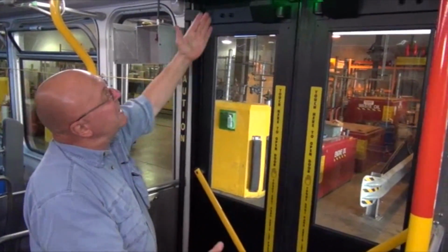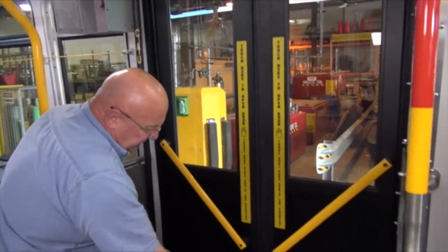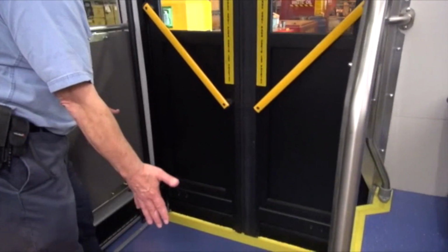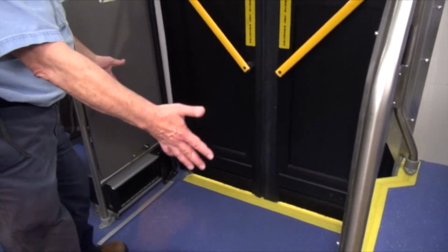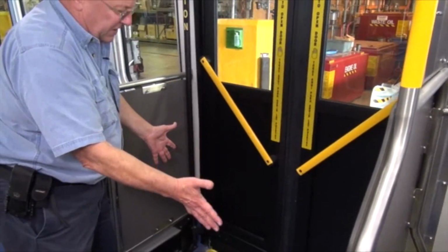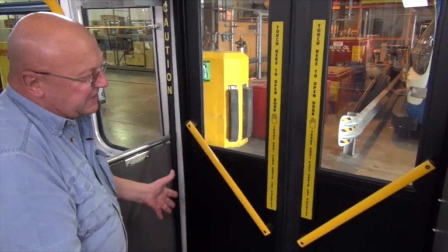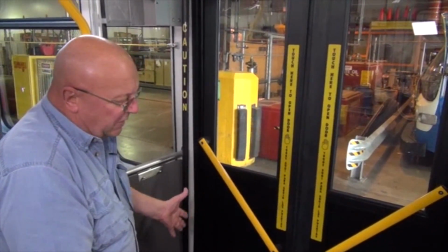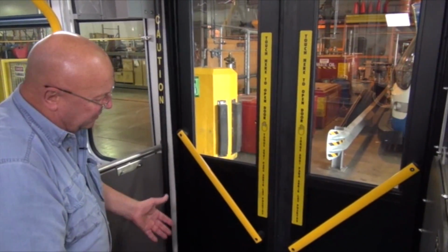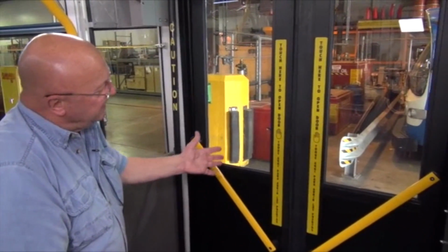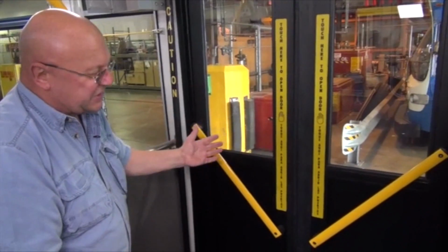So when we initialize the CLASS system and apply power, we want to make sure that this area 3 feet in from the door is clear of any foreign objects such as step ladders or briefcases, things like that, because in the event there is anything there, it's going to pick it up and put it into the target tables. This is only a temporary thing, as when they power down it will be removed from the target tables, but it does have the effect of adding additional targets and the potential for added dead zones.